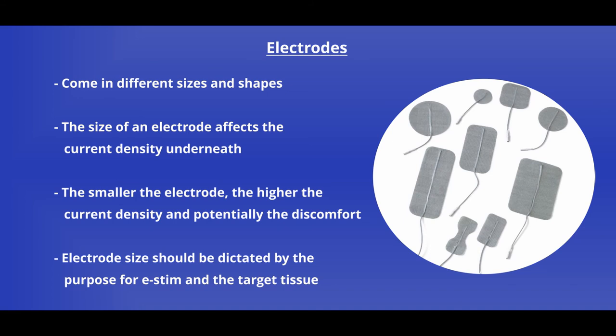When it comes to electrode size, it's very important to understand that the smaller the electrode, the higher the current density and the more potential for injury. With larger electrodes, that current gets spread out over a larger area. Typically, larger electrodes are more comfortable for a patient. Sometimes our e-stim treatment is more effective when we have focused current under a smaller pad, and there are some times when a larger pad is more effective for our treatment goal.